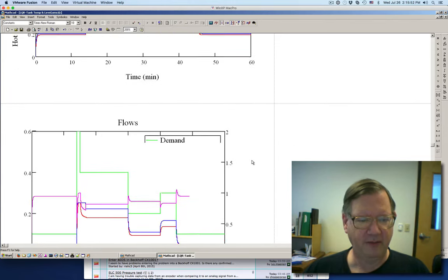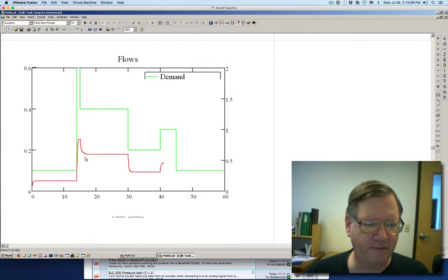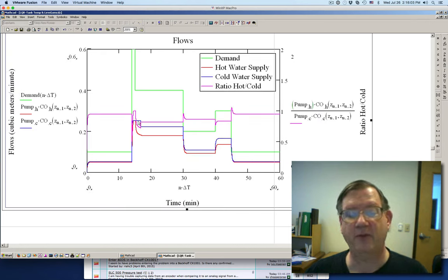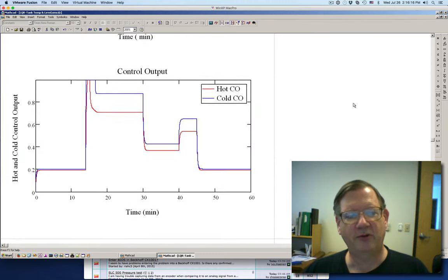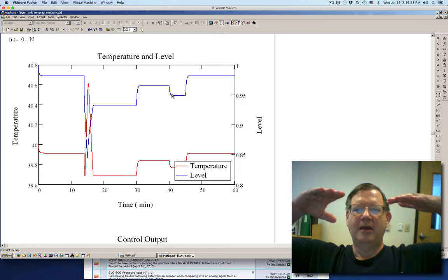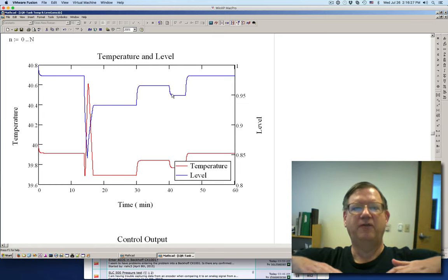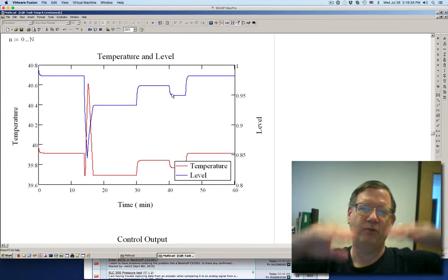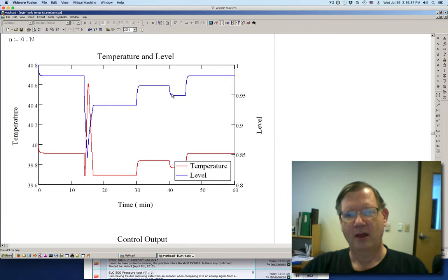So, here you can see the demand. And this is truncated off. This is truncated here because we just don't have any more flow. The pumps are running as high as they can. But still, you can see that it controls the level quite nicely. It's also desirable to keep the level up as close to one meter as possible, because like I said, as the level goes down, a little change in flow is going to change the temperature. Well, at half a meter, it's going to have twice the effect on temperature as it would at one meter, because you have more fluid to try to either heat up or cool down.